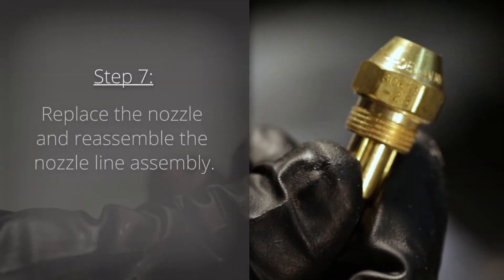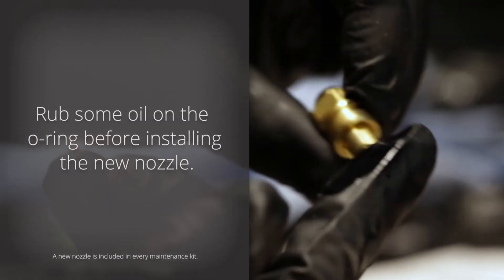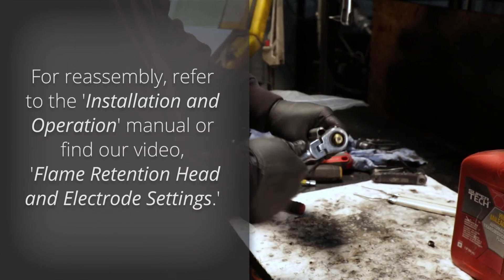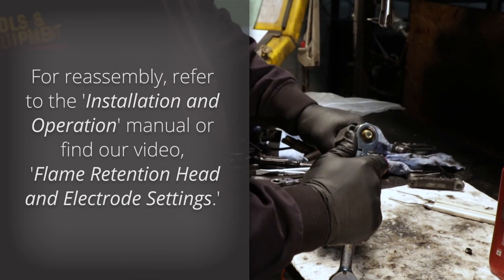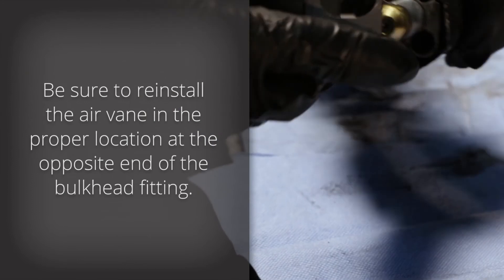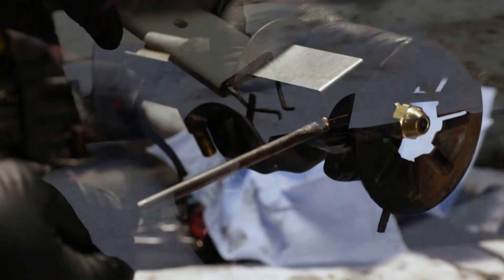Step 7. Replace the nozzle and reassemble the nozzle line assembly. Rub some oil on the o-ring before installing the new nozzle. For reassembly, refer to the installation and operation manual or find our video on flame retention head and electrode settings. Be sure to reinstall the air vane in the proper location at the opposite end of the bulkhead fitting. Incorrect installation could result in an off-center flame which may damage the heat exchanger and void your warranty.